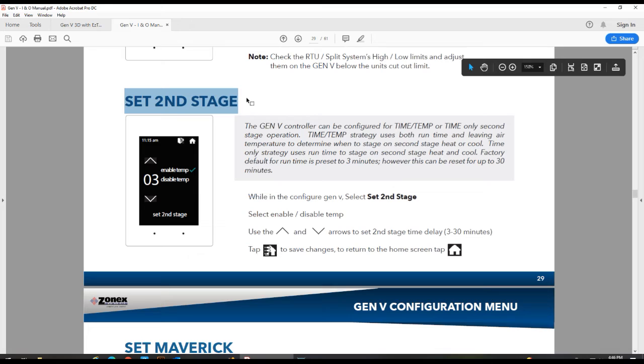Set second stage. This is a time and temp control. So you can go ahead and adjust the time that we look at the temperature limit on the system. So for example, if you're making a cool call, after 3 minutes we will check the temperature. And if it is above 58 degrees, we will then allow second stage to energize and continue to bring in additional cooling. If it's below 58 degrees, we'll leave second stage off and continue cooling on the system. If you want to delay the second stage from being looked at, you can adjust it anywhere from 3 to 30 minutes.